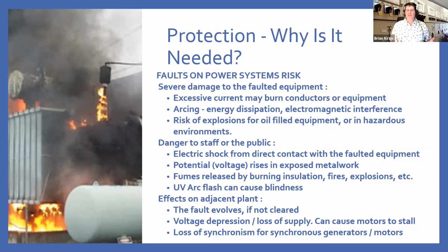Secondly, any staff or public in the vicinity are in danger of electrical shock, either directly by contact with the equipment or even indirectly because you could induce a voltage in exposed metalwork nearby. They also, as you can see here from an oil fire, can produce fumes either from the oil or from insulators, and these can be toxic as well. So you may need to clear areas when this happens. And UV arc flashing can happen, and this can actually cause blindness if observed directly.